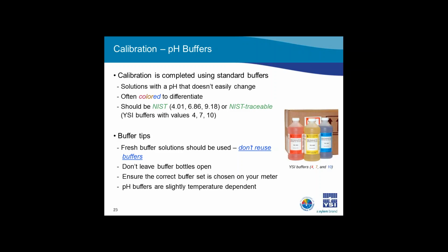In order to avoid contaminating your buffers, make sure you thoroughly rinse your sensor with deionized water and blot dry with a chem wipe between calibration points. As a best practice in the lab, you should triple rinse with DI water between calibration points. Also, as a good laboratory practice, you should definitely not reuse buffers. Once buffers are used for calibration, they are assumed contaminated. Reusing buffers can lead to slow responding pH probe performance or the inability to calibrate at all. This reuse can also make it difficult to determine whether the probe or the buffers are actually causing the pH calibration failure.